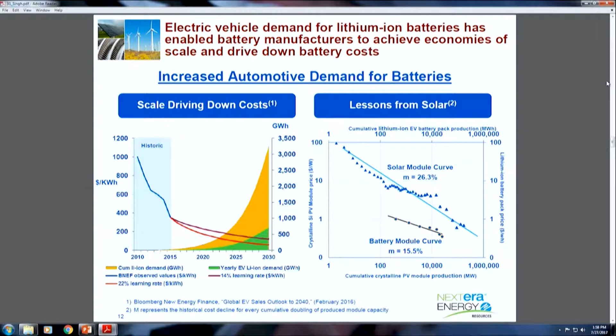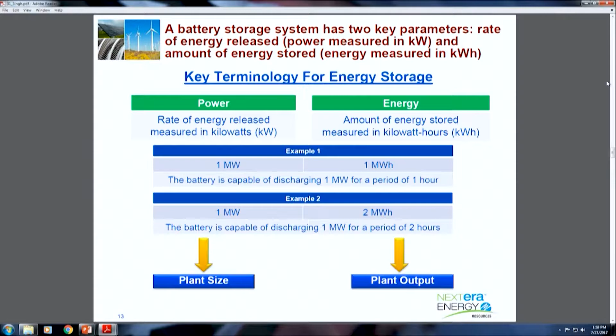I wanted to highlight a couple of terms we use in battery space. When we buy a battery, we are buying energy - there's energy content within the battery. We are buying kilowatt hours or megawatt hours. So usually we define, okay, what's a battery cost? People say $1 per kWh - that's what I'm buying. The other piece is the power, which is the rate of discharge of that energy over time, and that's typically driven by the size of the inverter. The rate at which you release energy is the power.